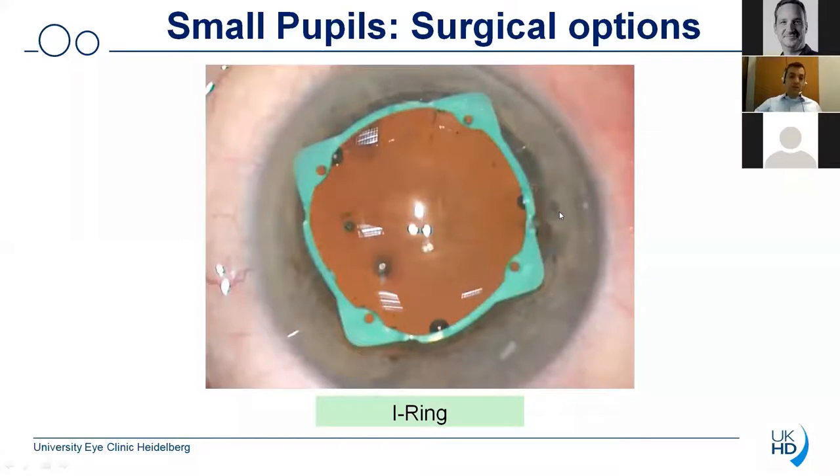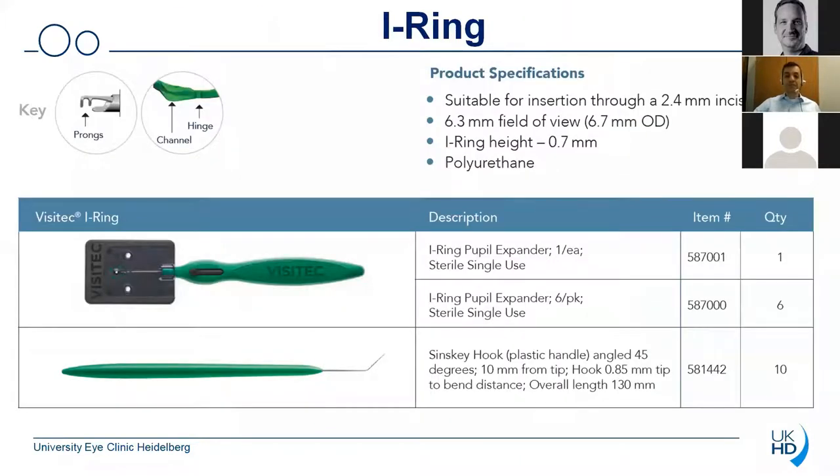The device that I would like to talk about today is the I-Ring, and I think most of you have either seen it before or maybe have had some experience with the device. A great advantage of the device is certainly the fact that it's suitable for an insertion through a 2.4 millimeter incision. You do not require any additional incision and you also do not have to enlarge your incision. You just do normal cataract surgery with your normal incision and you can use that device. The I-Ring allows you a 6.3 millimeter field of view which is indeed quite large.